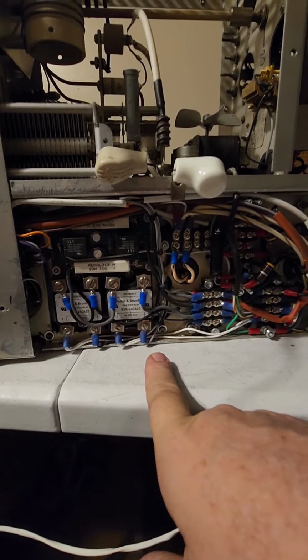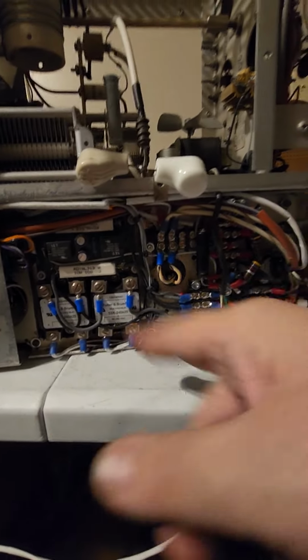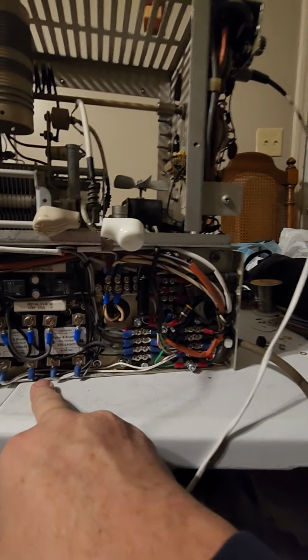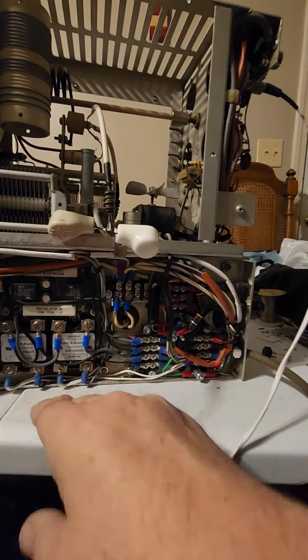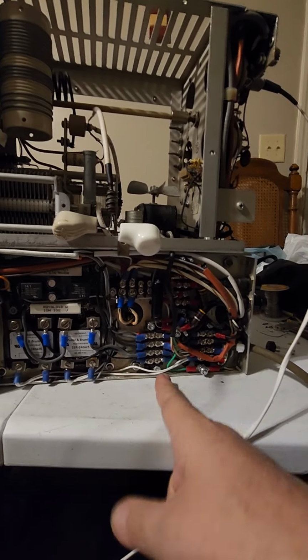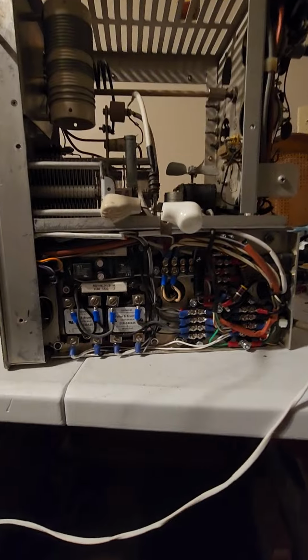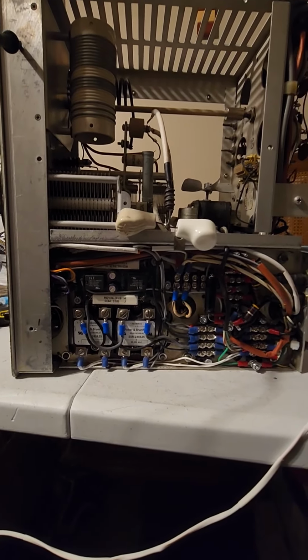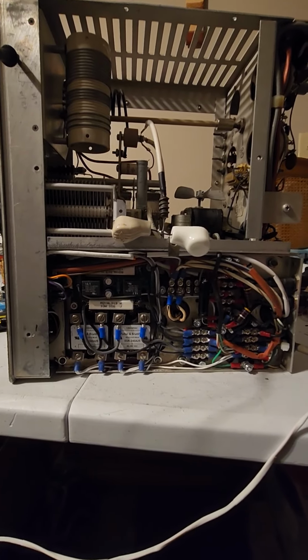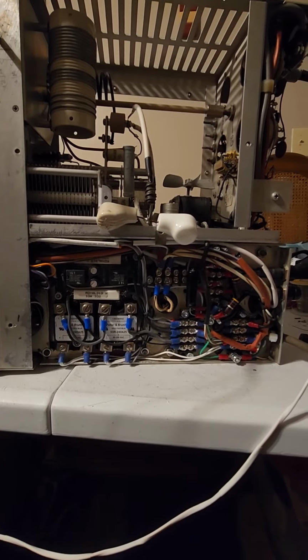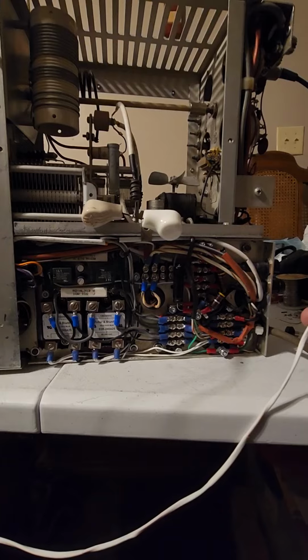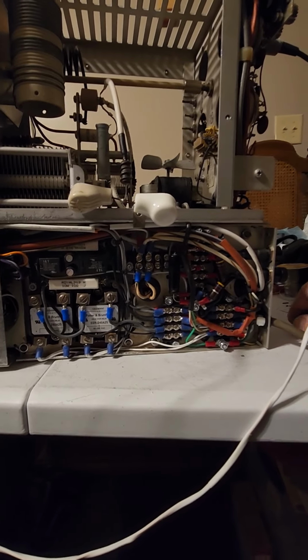Because the solid state relays are AC line controlled. There's a circuit A and circuit B through the normal Collins system, which I've kept. Circuit A's AC comes in through the switch to the circuit B side solid state relay, and I did the same with the B side, taking AC out of the switch to control the A side. So I've cross-circuited A and B to control each other's solid state relay. If you lose phase, power, or the fuse on circuit A, it'll kill circuit B, so there's now no power to turn on the A solid state relay, and vice versa.